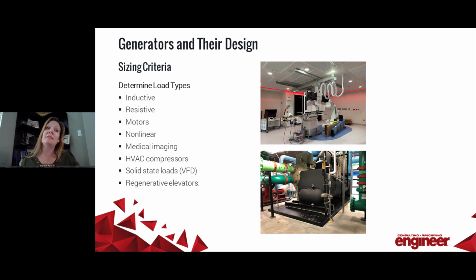By contrast, nonlinear loads such as VFDs or computers really create harmonic voltage distortion. This is different from the voltage dips and transients that the inductive loads create. Nonlinear loads generate harmonic currents, which flow through the alternator's source impedance. And even regenerative elevators must be considered since they exert energy back into the system. A typical generator can assume around 10% of its nameplate rating of regenerative load types.